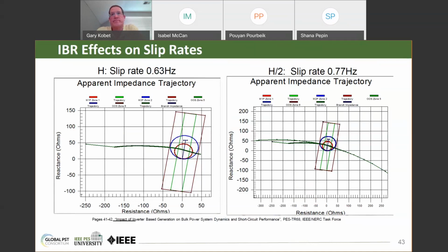In cases where the power swing blocking logic is looking at, in most cases, the time it takes for an impedance trajectory to pass between blinders, if those swing rates change appreciably, then it will require adjustments in the power swing blocking settings. So just something else to think about there.